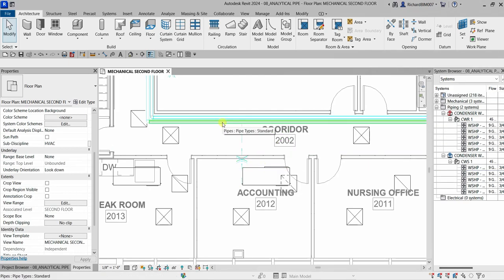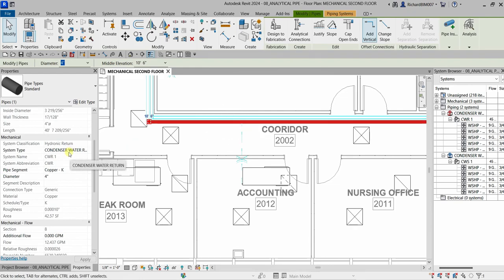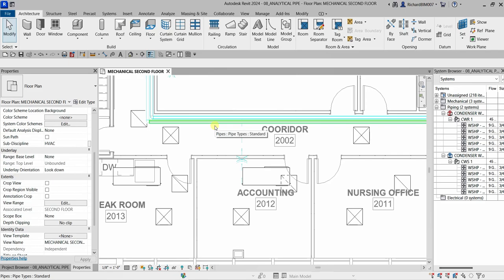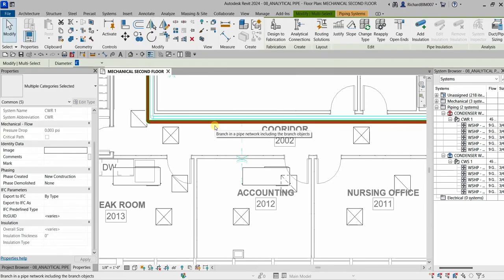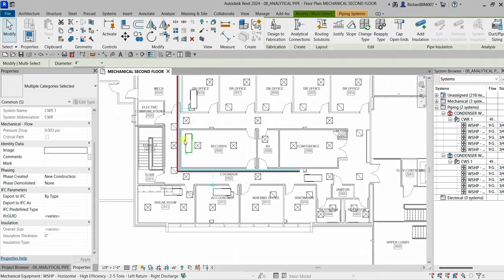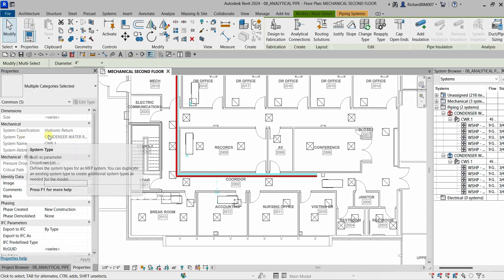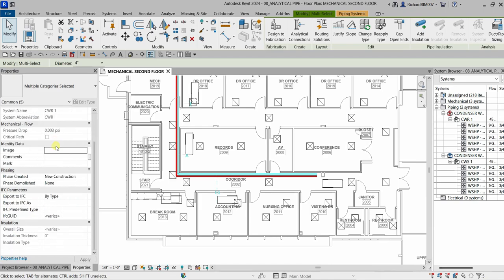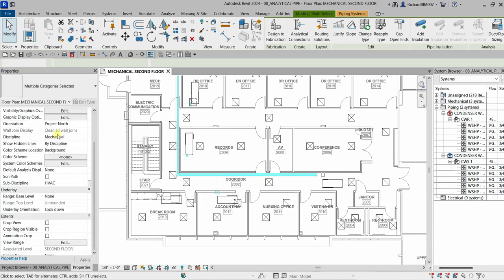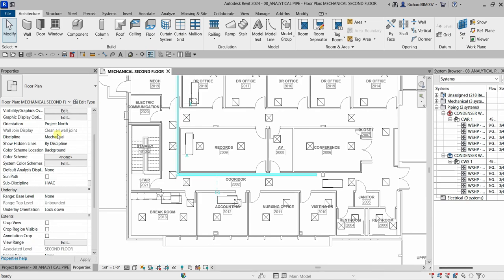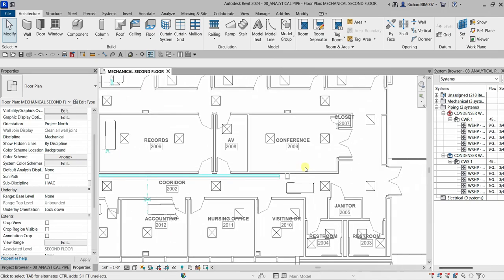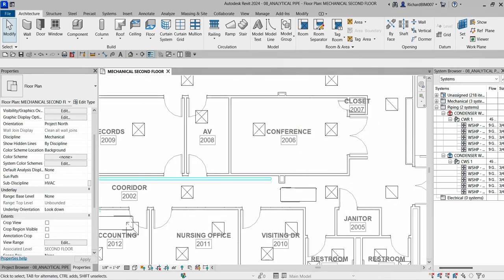If I select one of the return pipes, you can see this is the condenser water return. You can also hover your pointer over a pipe and press Tab to cycle through selections — this allows you to select pipe connections, and it will tell you the particular system, which is condenser water return. Be aware that Revit can calculate all parameters since analytical connectors are connecting all components in the system. That's why it's very important to create a system in your model.